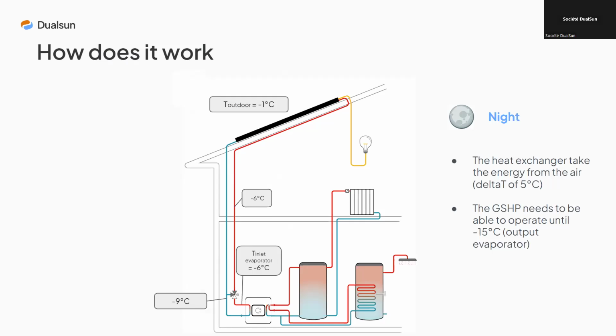It's important to understand that the heat pump regulates itself to ensure that the temperature at the evaporator coil inlet is low enough to be able to recover heat from glycol water at -6 degrees for this example. And it does this all the time as long as it's not too cold outside. You should also bear in mind, of course, that the set point downstream on the production circuit side is fixed. And so the heat pump has to do what it needs to do to meet the requirements.